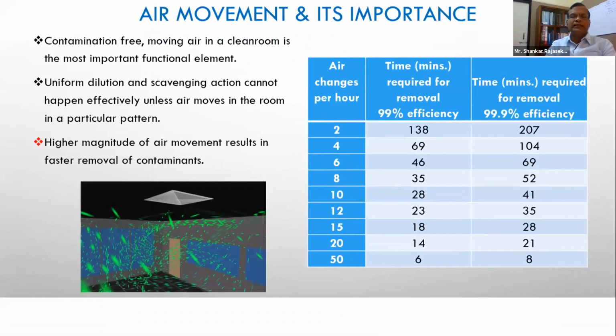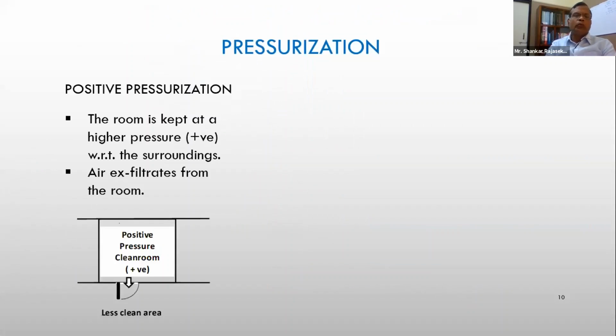So we talk about pressurization. There are two possibilities. One is we can positively pressurize a room, where we supply a larger quantity of supply air and take out a lesser quantity of return air from the room, whereby the extra air exfiltrates from the room, and the exfiltration velocity takes care of preventing the contaminants from coming inside.